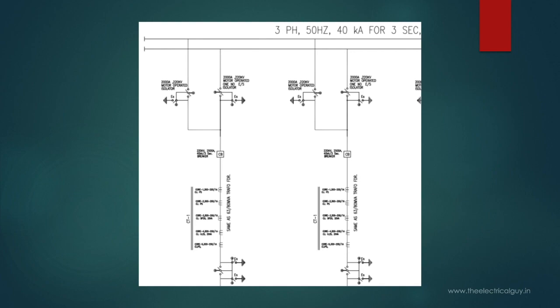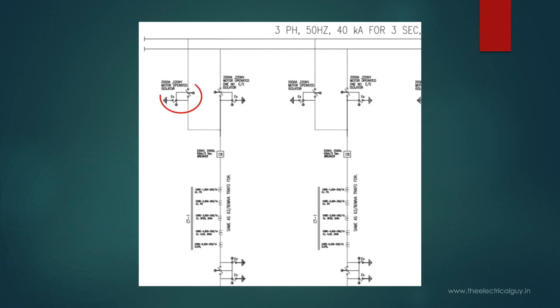So in case if one of the bus fails, we can take the supply from another and continue to deliver the power. And to reroute this power from one bus to another, disconnectors are used. Here you can see we are taking power from main bus one. But because of some reason we have to shut down this bus. In such cases, we can open this disconnector and then close this disconnector and turn on the main bus two.